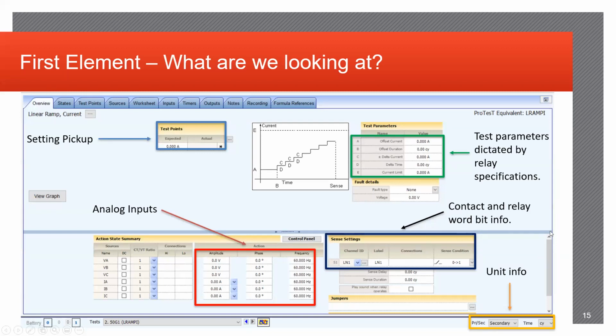This sense setting is where we'll be utilizing the test set's input. So basically what we'll be doing is running this test. Your sense connection is actually going to be connected to that spare output that we're going to be utilizing from earlier, setting the spare output to the 50G1 element, and that's what will be utilized when you're running your tests. It's going to close that output and cause that input to pick up on your test set, and that's what it'll be sensing. As well as your unit info down here, this is basically determining whether this is going to be primary or secondary values that you're going to be injecting, as well as what the time values would be, whether that's in cycles or seconds.